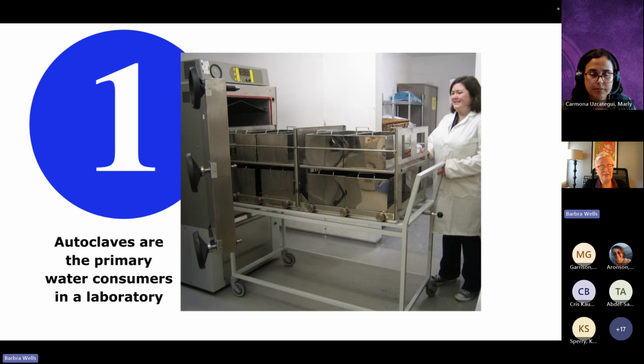Third, autoclaves use water to create a vacuum. Water serves as the operating fluid in a liquid ring pump or a Venturi ejector pump that's used to run vacuum cycles. Typical autoclaves come standard with vacuum features because they're required in hospitals and other high throughput settings. But not all laboratory loads even need a vacuum cycle. Many labs never run one. In any case, extra water runs down the drain at the end of every vacuum cycle.